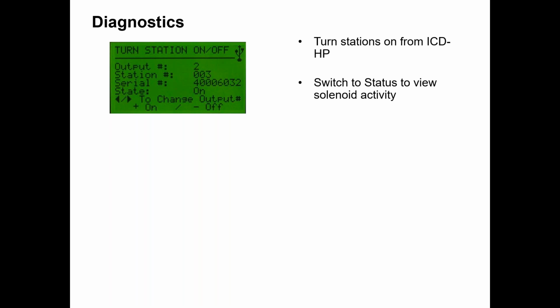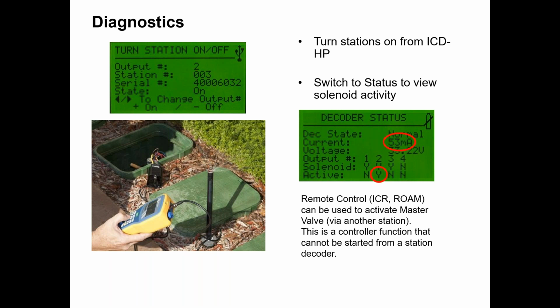Another handy feature is you can turn stations on from the ICDHP. So if you go to the turn stations on and off and you turn it on, then I would go to the status to view your solenoid activity. And typically, if you have a solenoid and it's turned on, you'll see the milliamp jump because now it's supposed to be drawing more power, and it'll typically jump 40 milliamps, somewhere in that range. By this one going to 53, it's a little bit more, but it's nothing catastrophic. If it goes to 150 or stays down at 3, you probably either got a shorted output or the solenoid might be damaged itself.